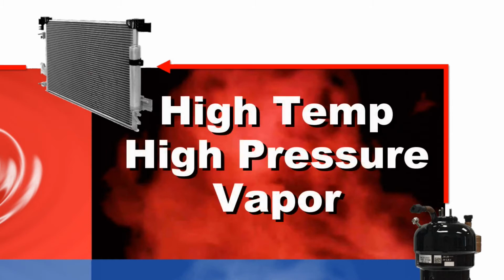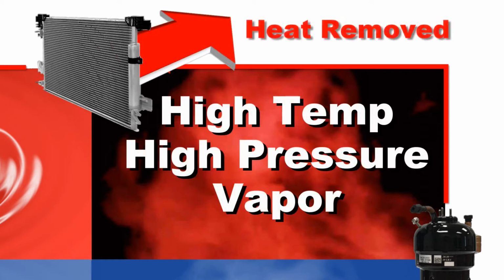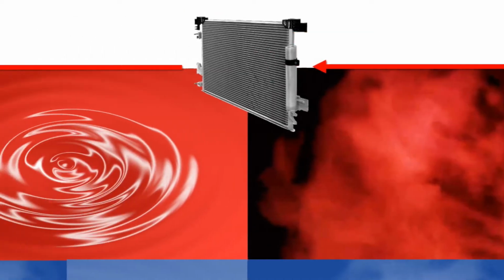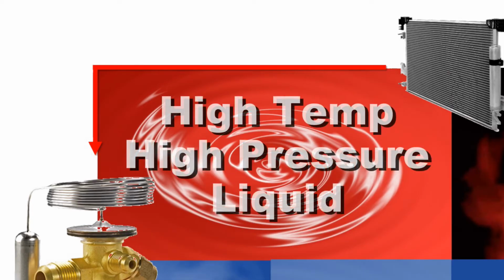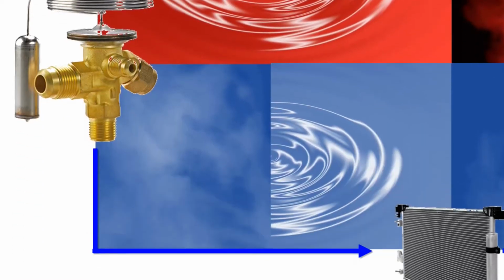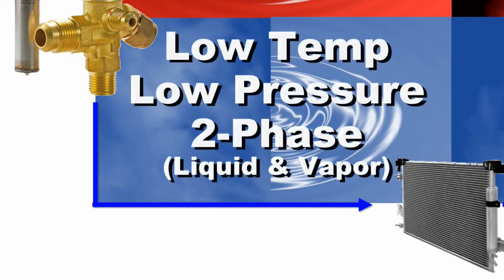vapor. This vapor enters the condenser where heat is removed to either air or water. As the heat is removed, the energy stored in the high-pressure gas is released, and the refrigerant gives up its latent heat as it reverts to a hot liquid. This hot, high-temperature liquid exits the condenser and enters the expansion valve, where it undergoes a pressure drop causing some of the hot liquid to vaporize, lowering the temperature of the refrigerant stream.